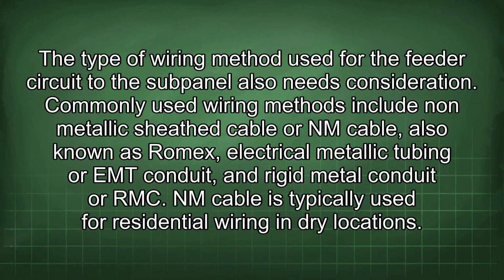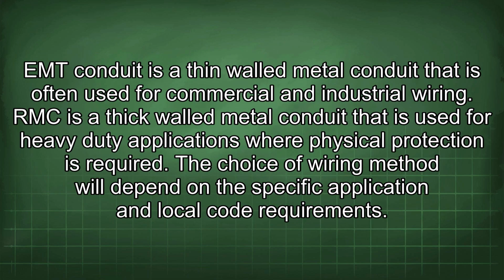The type of wiring method used for the feeder circuit to the subpanel also needs consideration. Commonly used wiring methods include non-metallic sheath cable or NM cable, also known as Romex, electrical metallic tubing or EMT conduit, and rigid metal conduit or RMC. NM cable is typically used for residential wiring in dry locations. EMT conduit is a thin-walled metal conduit that is often used for commercial and industrial wiring. RMC is a thick-walled metal conduit that is used for heavy-duty applications where physical protection is required. The choice of wiring method will depend on the specific application and local code requirements.